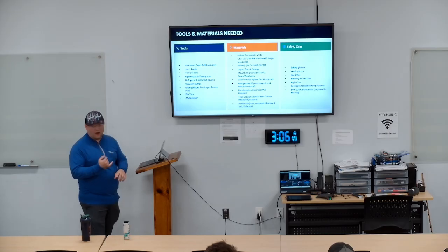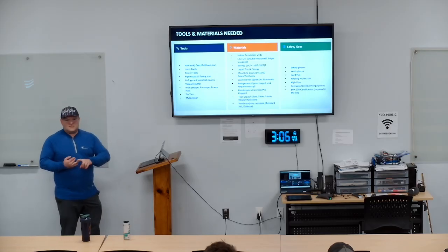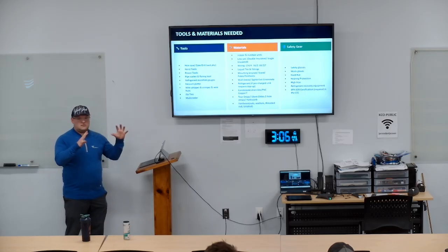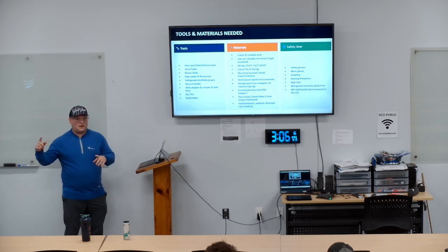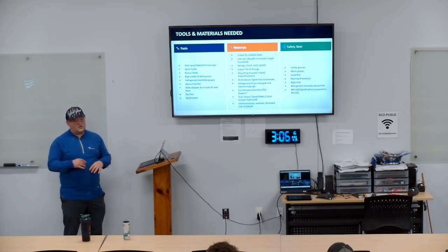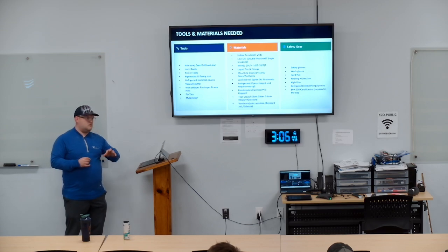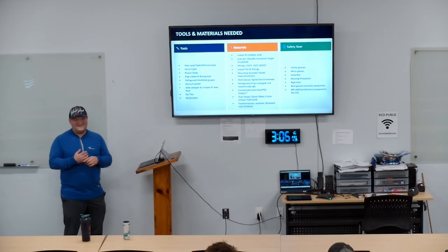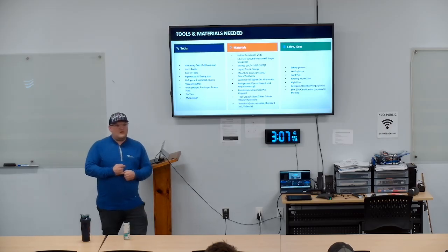Anytime we do it on wall mounts or sets, the reason we're double insulating is because those indoor heads have no metering device. So when it comes through, it's coming through just like it would on the suction side, and the temperature is going to vary from the space it's running through. If it's not insulated, as soon as you get a 30-degree swing, so if it's a 20-degree line coming through a 70-degree space, anytime it's over a 30-degree swing, you're getting condensation. And then you're going to get a phone call that says, hey, my ceiling's falling through because it's a soaking wet line.